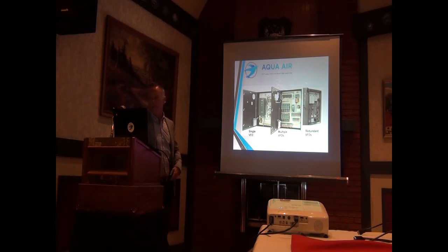We're going to talk a little bit about redundancy in fan walls in general. The good thing with fan walls is if you have 10 fans and one fails, you still have 9 fans and motors that are operational. Your VFD will adjust the other fans that are operational to try and meet demand. In most cases, when you're designing an HVAC system, you're designing for your winter and summer extremes, but that's not where your system most of the time is running. It's running somewhere in between. So in most cases, if you had one fan fail in a fan wall application, the other ones will speed up. You wouldn't even notice it probably meets set point.